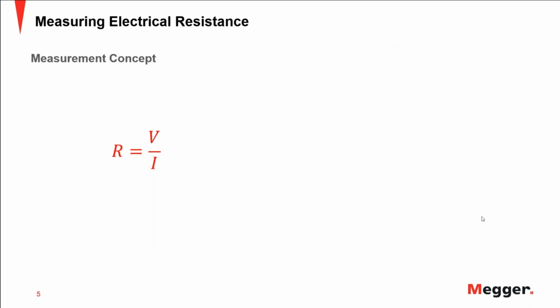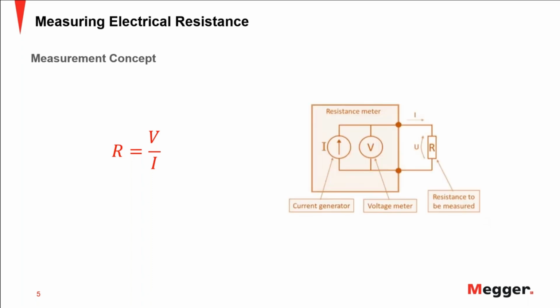So moving on to the concept of the measurement, from the previous slide where I was showing the specs of the typical instruments, I always talked about voltage and current, because that's what we do when we want to measure resistance. We apply a voltage and we measure a leakage current, or we apply a current and we measure a voltage drop, and with those 2 parameters we can calculate the resistance. So basically that's what we're going to be talking about during this presentation.